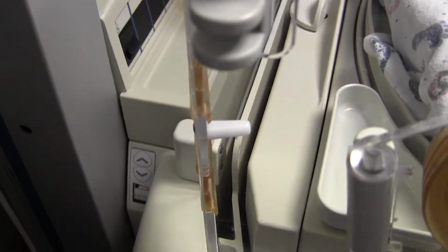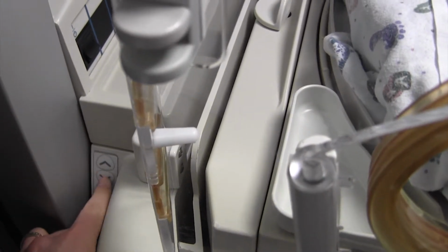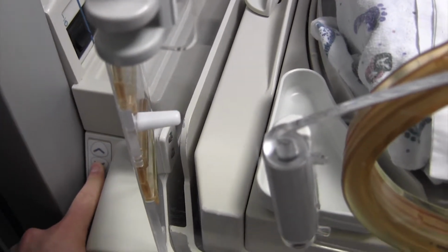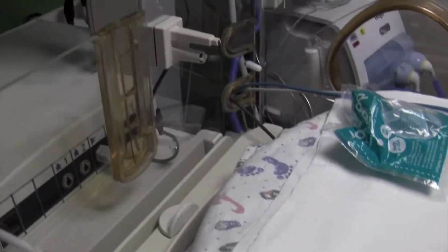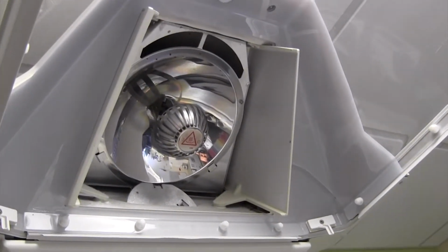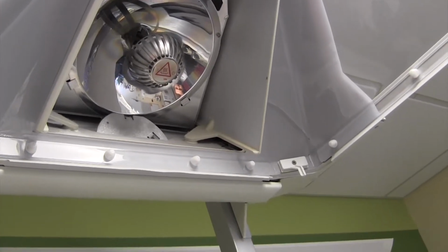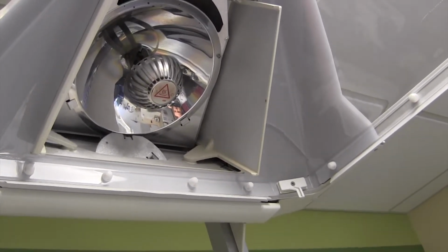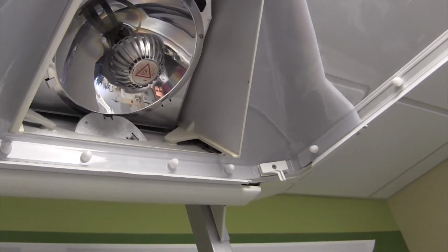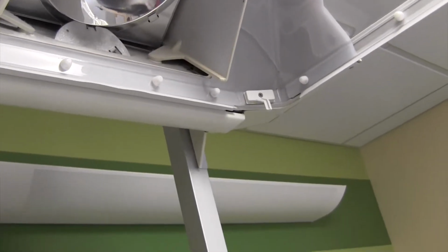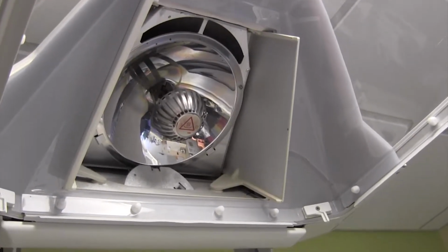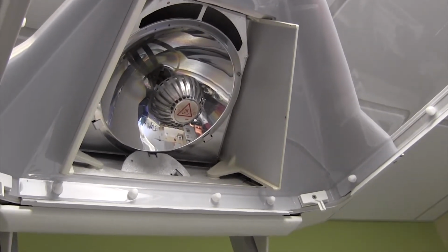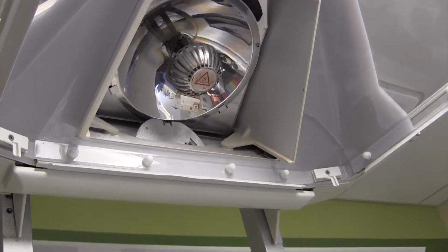That top can also be opened. If you look on the side of the incubator, there's a little set of buttons. The top one opens, the bottom one closes, so if we push that button, we'll see that top starting to come down. The other thing I would point out as we're opening up the top, if you look up at the very top, as you get the incubator all the way open, you'll notice that there's a radiant heater that opens up. You can imagine when that top is opened up that we can't contain the heat within the incubator, so that radiant heater is there to help provide some additional heat to keep the infant in a stable thermal environment when the top is open.